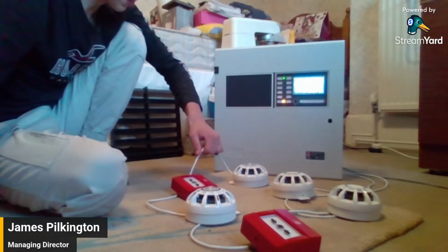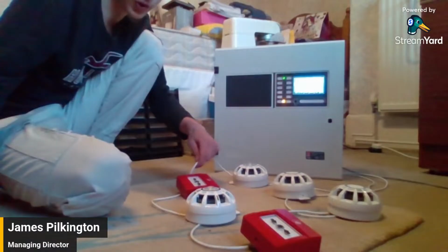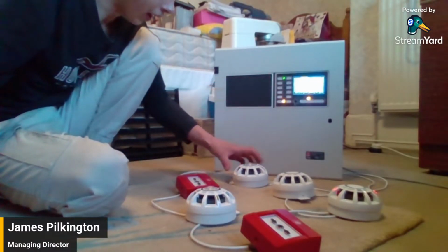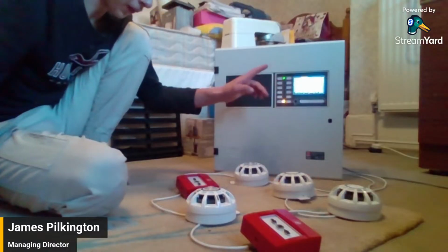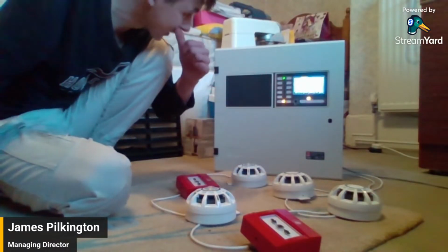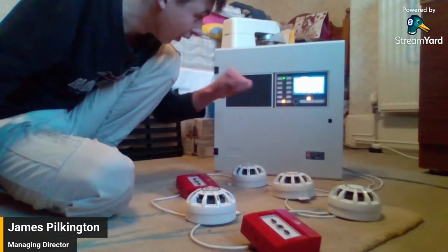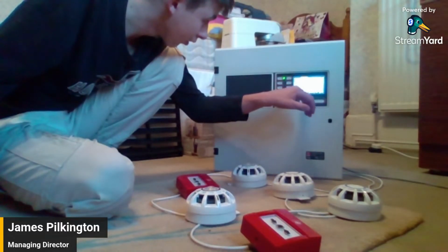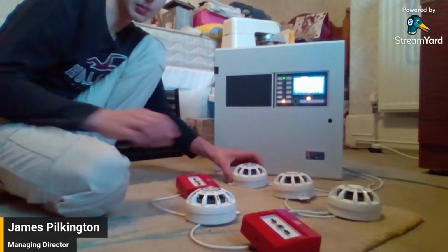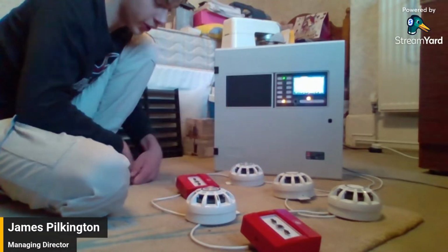Again, I've powered the panel down, I've transported this, and I've taken the loop. Oh, there we are. That's coming up better now. So I think that detector might not have been seated on its base correctly, because now we do have all the correct devices. So we're going to mute the beeper. I think this base had just come unseated during transport.